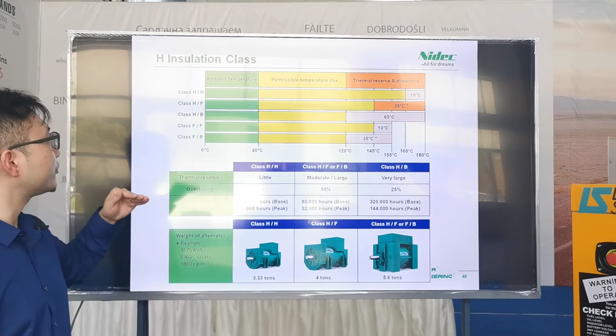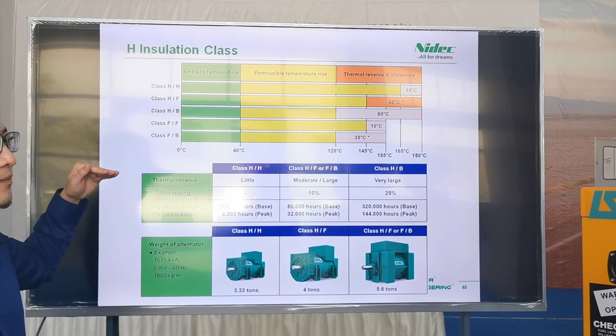About insulation class, there are actually two different concepts: one is insulation class, one is temperature rise class. Insulation class is the most critical factor for the longevity of the alternator, because normally the insulation life decides the alternator life.